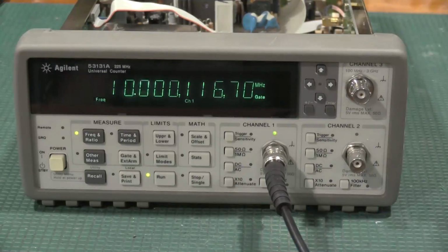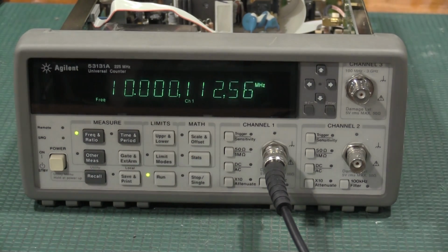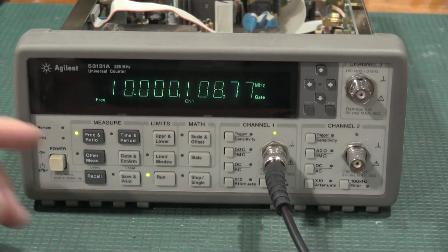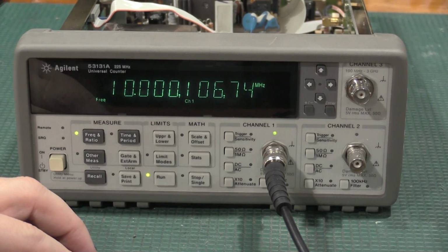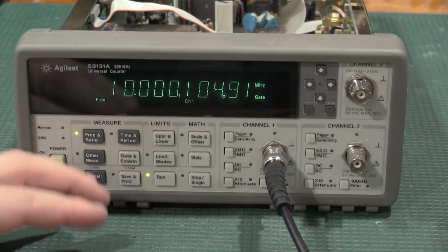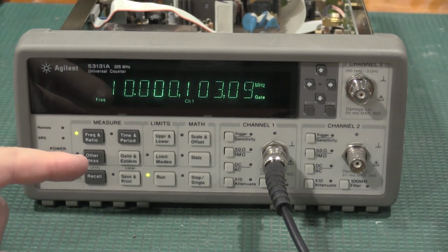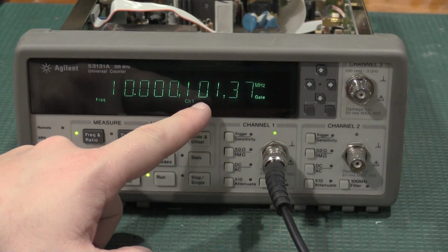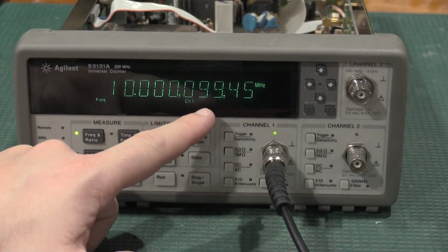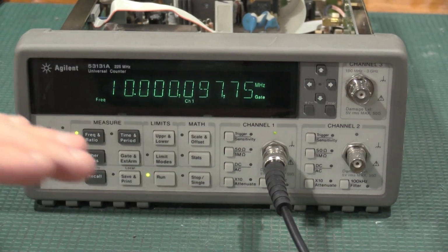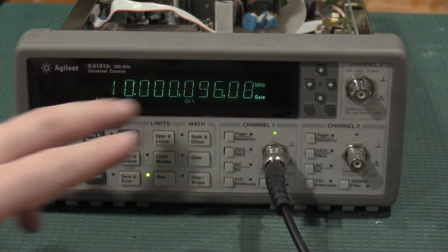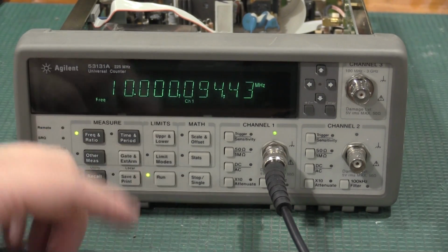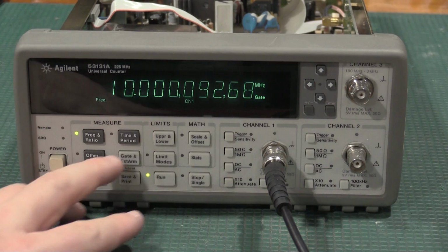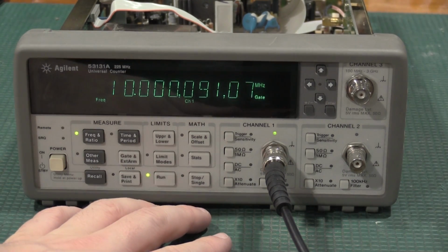So, just in the time it took me to talk about the rubidium, we've seen this come down quite a bit. That's the oven warming up in the time base. So this has been off for several weeks, or a week, while I was waiting on parts and things like that. So I need to let this oven warm up before I even do an adjustment. And as you can see, as I'm talking, it's still counting down. So the crystal's heating up, so it's going to kind of coast in. And this should stop right around 10 megahertz. Well, it should stop at exactly 10 megahertz in theory. So we'll figure out how far it is off.